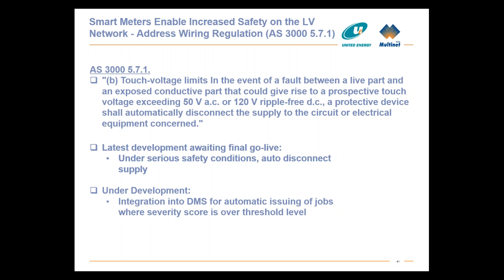We started using the same principle on house assessments, and we're in the last few stages of implementing this: the moment we detect a 50 volt touch potential, we can use the smart meter and issue an automatic disconnect from the analytics. We've already developed this code and it's going through the final phases of testing. Similarly, if customer severity reaches a certain point, we can electronically dispatch this to our DMS system and out to a fault truck.